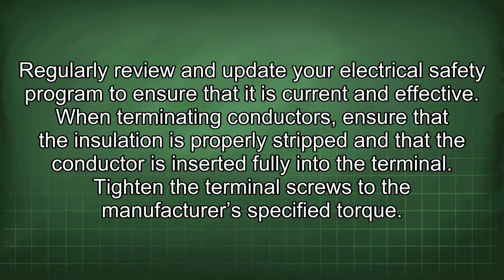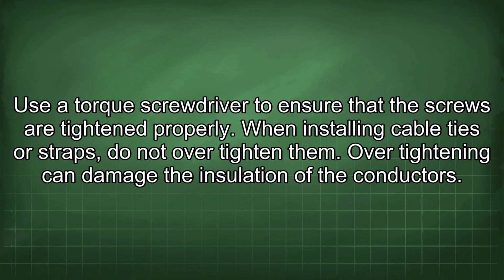When terminating conductors, ensure that the insulation is properly stripped and the conductor is inserted fully into the terminal. Tighten the terminal screws to the manufacturer's specified torque. Use a torque screwdriver to ensure that the screws are tightened properly. When installing cable ties or straps, do not over-tighten them. Over-tightening can damage the insulation of the conductors.